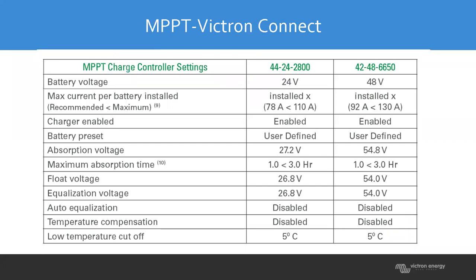So the Victron Connect is basically the same as the VE config. And you'd also want to look at your max current per battery installed. This could come into play as well if you had multiple MPPT charge controllers, like let's say you had 4 250-100s, that's going to max out and be more than the 130 or 260 in my case. So you've got to watch that, depending on the amount of MPPTs and the amount of capacity you have installed. So we're going to enable the charger.